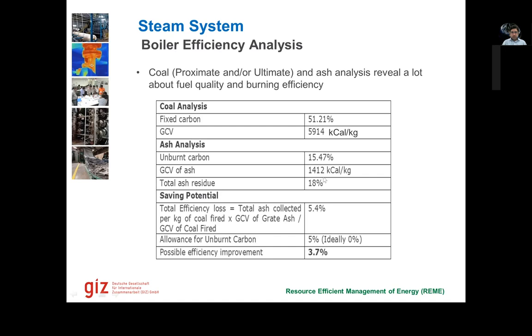So you just have to put in the coal analysis and ash analysis, and then it automatically calculates what percentage of loss we're making. What I usually do is provide an allowance for unburnt carbon, about 5%, because we cannot achieve an ideal zero unburnt carbon. And then we can have a possible efficiency improvement based on this.